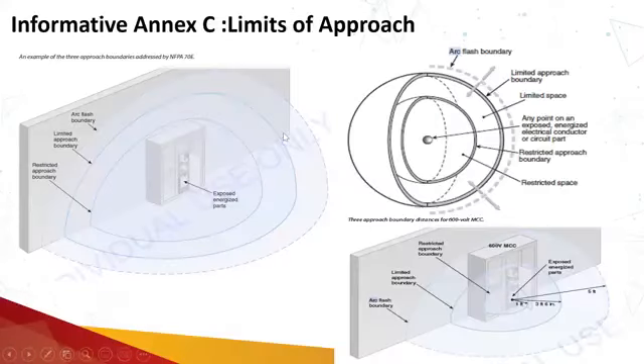So how are the limited approach boundary, restricted approach boundary, and the arc flash boundary calculated, and where will you find further information? You can turn to informative Annex C, which is basically the limits of approach boundaries. In this Annex C, you will find further information related to the limited approach boundary, restricted approach boundary, and the arc flash boundary.